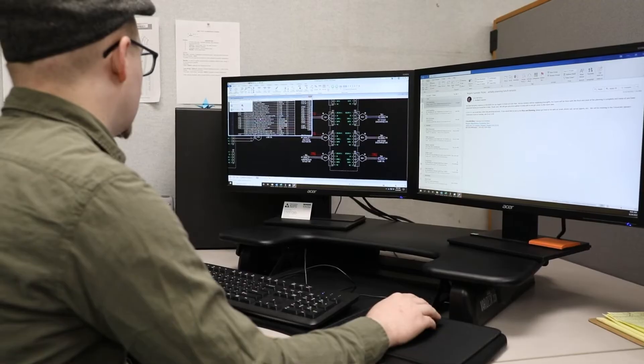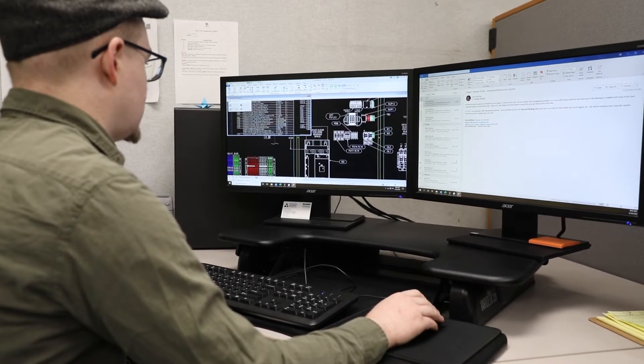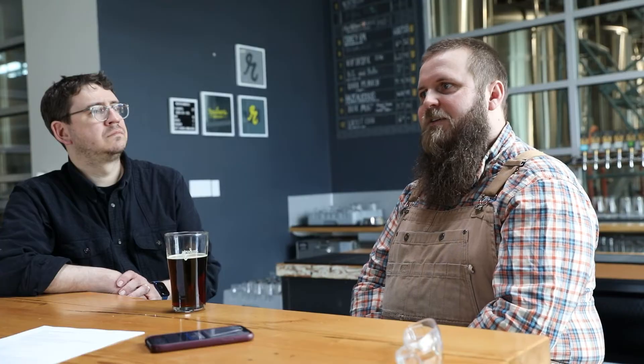I never actually mentioned that we were trying to get a particular flow rate of CO2 — I was saying we need this flow rate of nitrogen. And it turns out there's actually a difference there. So when we fired up our canning line, we were actually having some trouble keeping up. After a very quick phone call with the engineering team, they asked what purity level we were running at. The techs came out and made a quick setting adjustment on the nitrogen generator, and we got more than enough flow rates. Everything was wonderful.